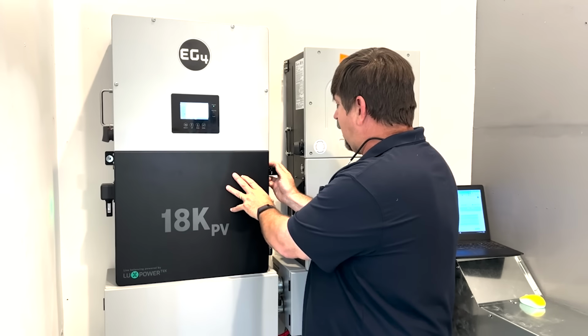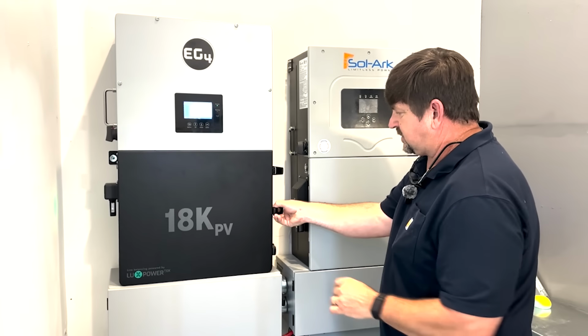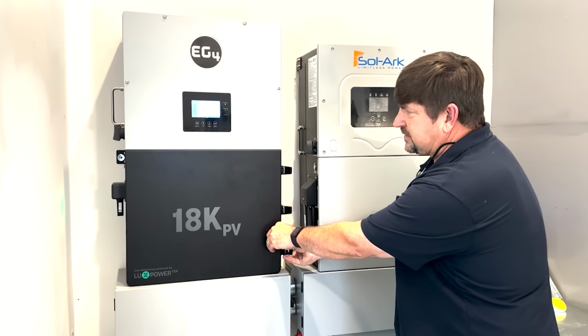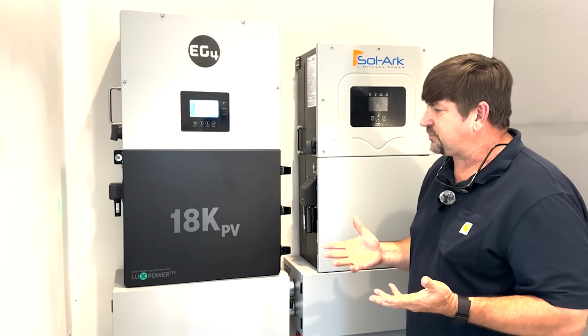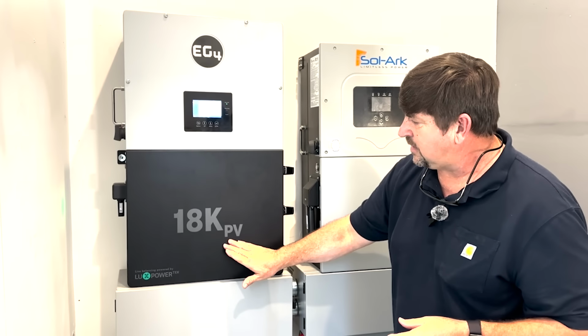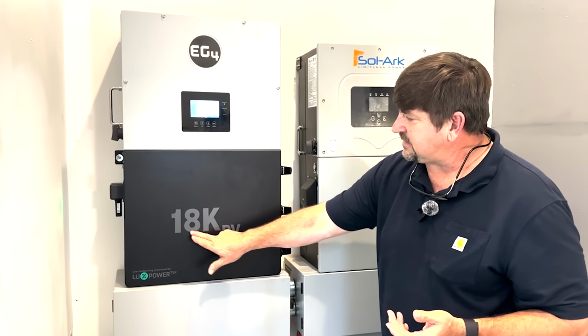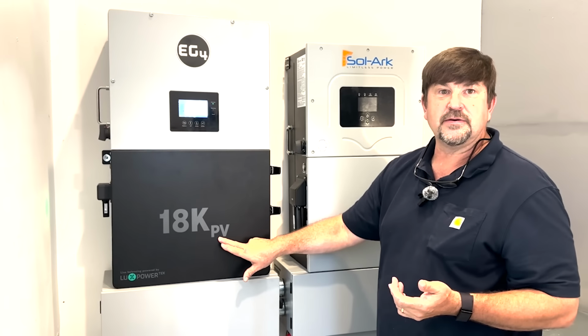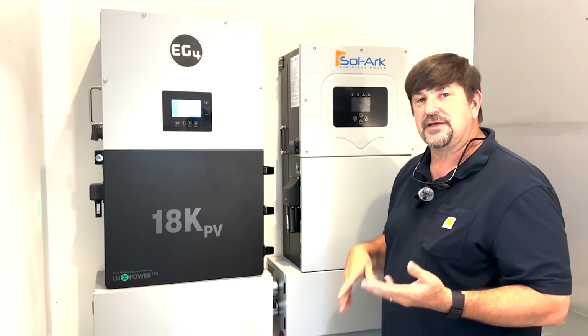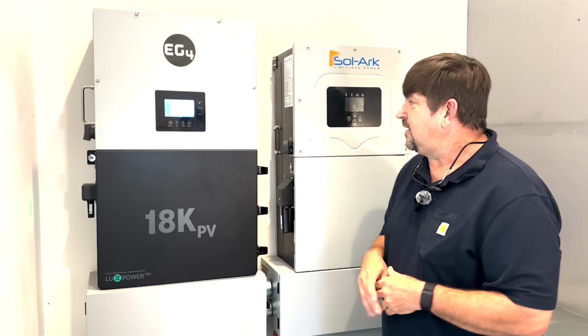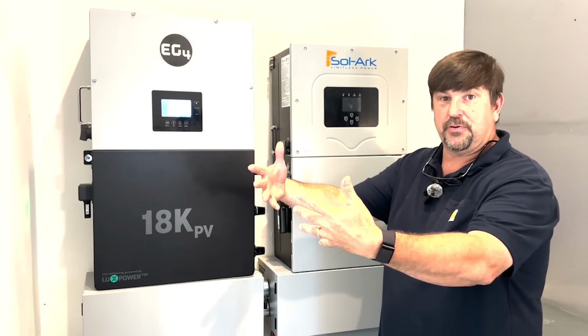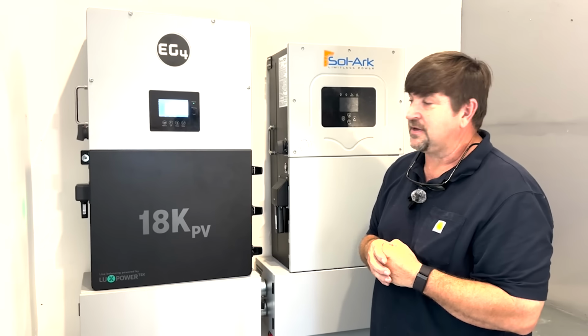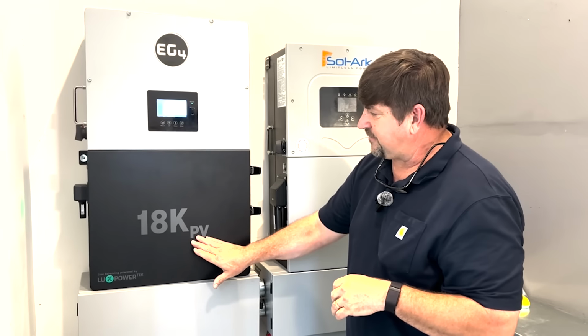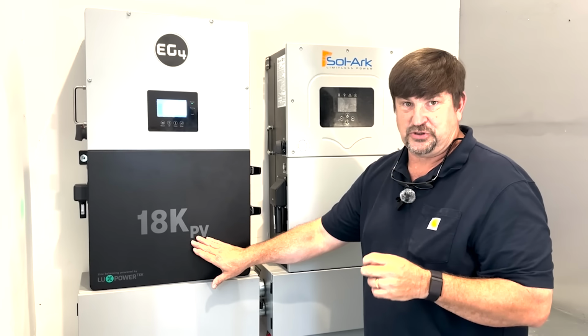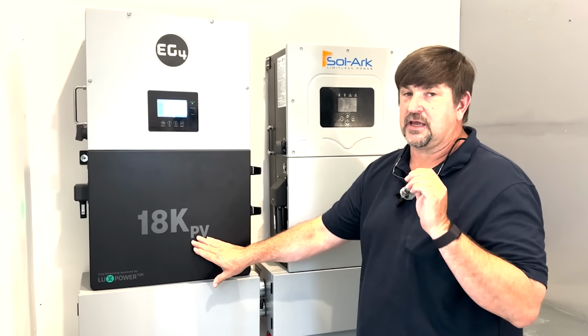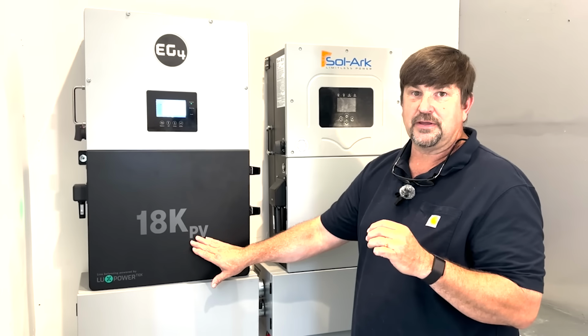I want to talk about the naming convention before I get into the inner workings. The confusing thing I always wonder is why they're using this naming convention. They're not hiding anything - they tell you it's 18,000 watts of PV. That's straightforward, except most inverters in the industry are rated on their AC output. The 15K actually outputs a full 15K continuous, but the 18K-PV is really a 12,000 watt machine - a 12 kW machine that can never produce more than 12 kW on the AC side.